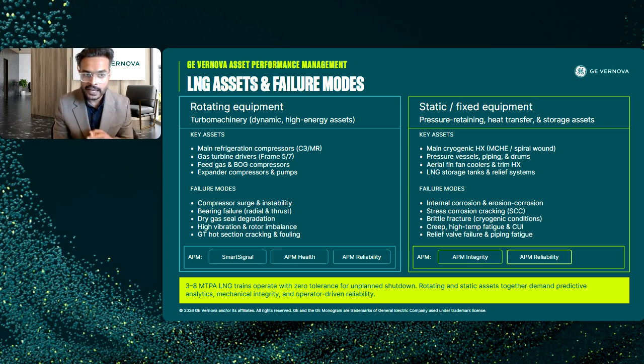We have the main refrigeration compressors, the propane and mixed refrigerant compressors, and the gas turbine drivers. Most of the cases, these gas turbines would be GE Vernova frames, including the 5, the 7Es, and the 9Es, which drive some of the super LNG trains across the globe. We also have the feed gas and boil-off gas compressors, and the expander compressors and pumps. So it's clear we have a variety of turbo machineries operating at high speed.